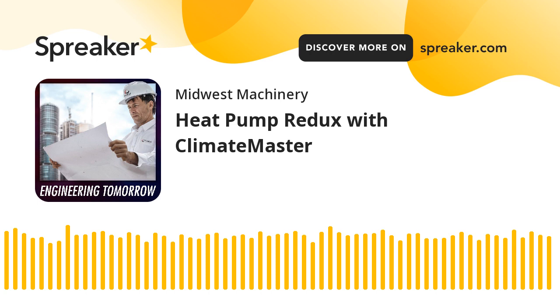The refrigeration circuit of a water source heat pump consists of the following components. We have a refrigerant to water heat exchanger. This heat exchanger can be a tube and shell, or a brazed plate design. ClimateMaster utilizes the tube in tube, also known as a coaxial refrigerant to water heat exchanger. The second is a refrigerant to air heat exchanger. This is a fin tube coil similar to any DX coil on an air-cooled rooftop. The third component is a compressor. All heat pumps have at least one compressor, depending on their capacity. Compressor type and size all depend on the manufacturer and their performance requirements.